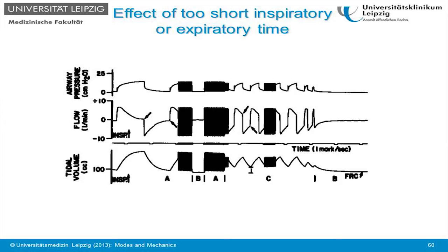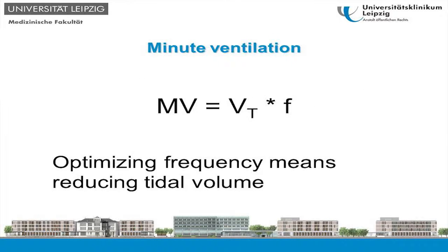So, if you decrease the inspiratory time too much or the expiratory time too much, you will see that the tidal volume decreases, and this is because the times have been shortened too much, and this can be seen on the ventilator screen if the flow is being measured, which may alert a clinician to change the ventilator settings to more fitting values. By doing this, you can at least optimize the frequency. You can find the highest frequency which can be run with the lung you have.